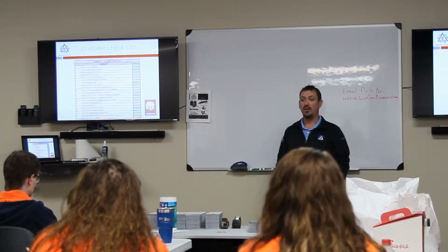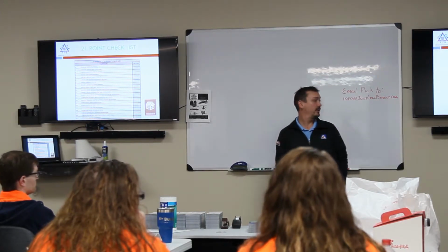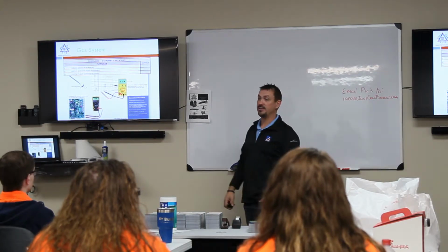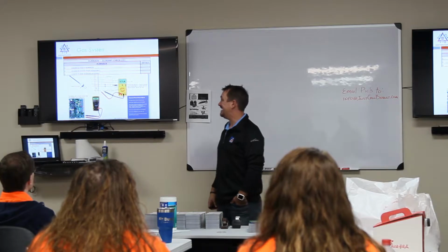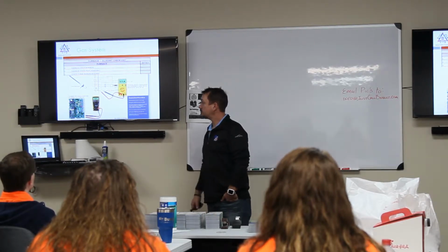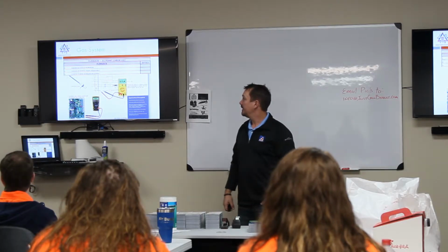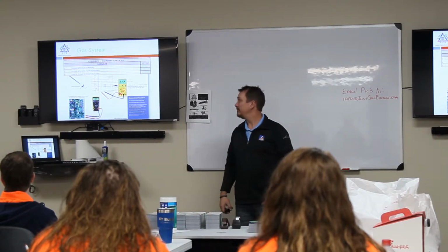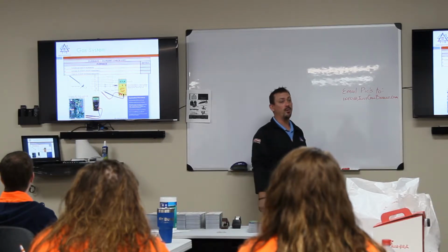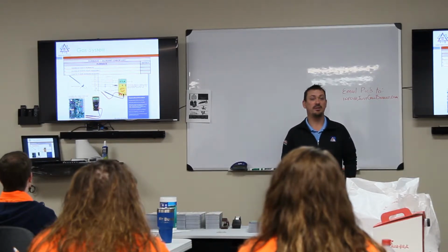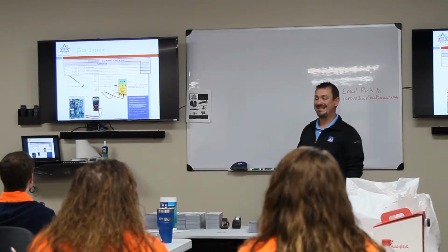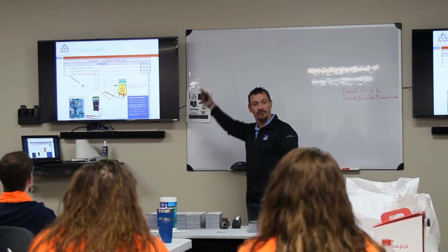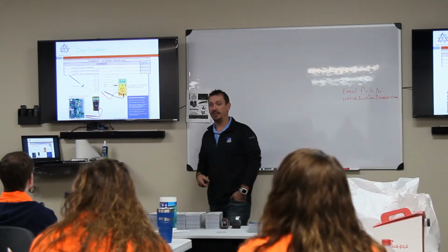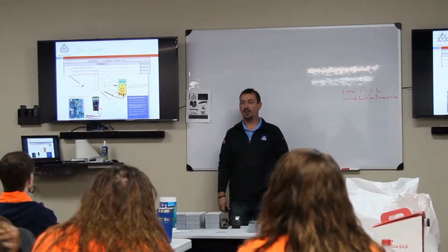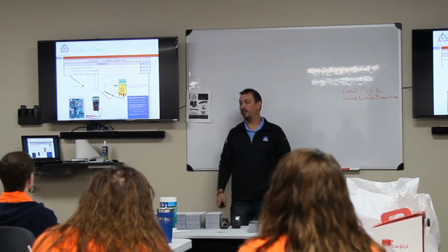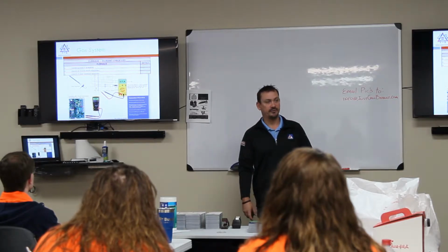And we're going to make sure we have a couple of key sections that we actually do look at and check. We're going to break it down into a couple sections, and the first section is the gas system. We're going to check the burners, the pilot assembly, and then the flame sensor. Now this is a 21-point checklist. There are going to be some things on here that are obsolete and that you won't necessarily run into much anymore, one of them probably being the pilot assembly. Those tend to be mainly all replaced at this point in time. I'm sure you guys probably are still running into a few of them, but they're very few and far between.